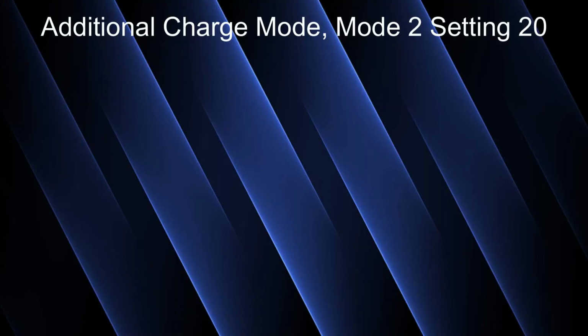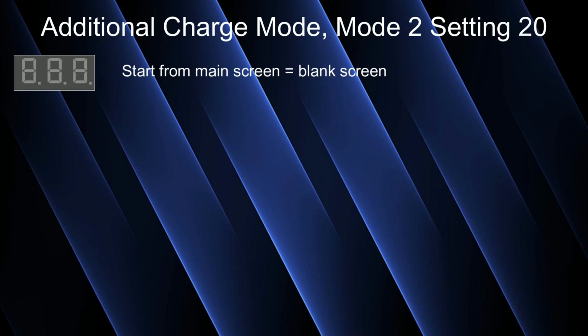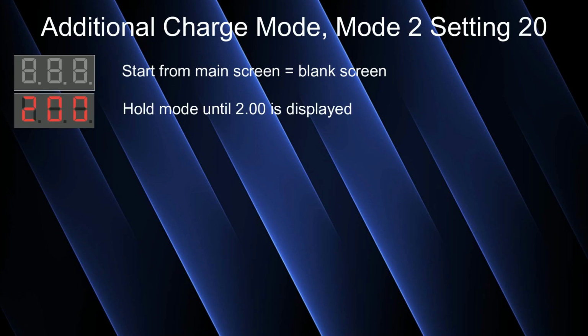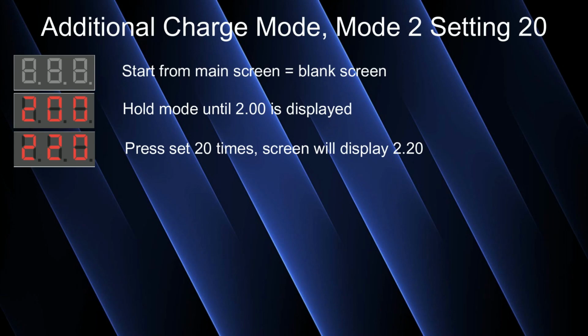On the newer board styles, you're going to again start from the main screen, which is a blank screen. You're going to press and hold the mode button until the screen flashes 2.00. Again, you want to go into service mode 2. And now we're going to go to setting 20. So you press set 20 times, the screen will simply display 2.20. It's much easier to follow how many times you've pressed the set button on the newer boards.